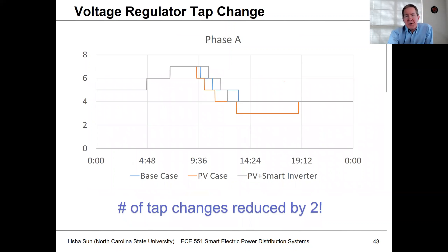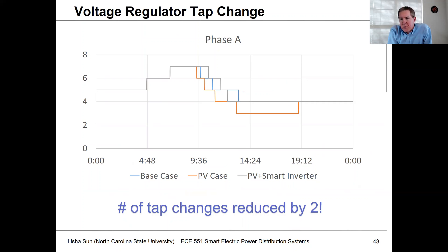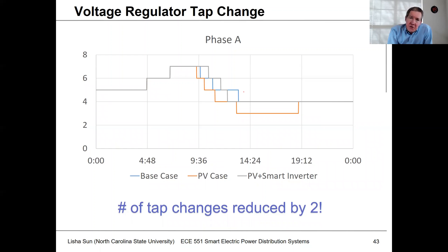You can also look at regulator tap changes, and as a result of smart inverter control, we're actually able to reduce the number of tap operations. In a way, if we had a lot of inverters out there, we may not need voltage regulators at all — if we choose our control points properly, we could inject vars to control voltages throughout the circuit.